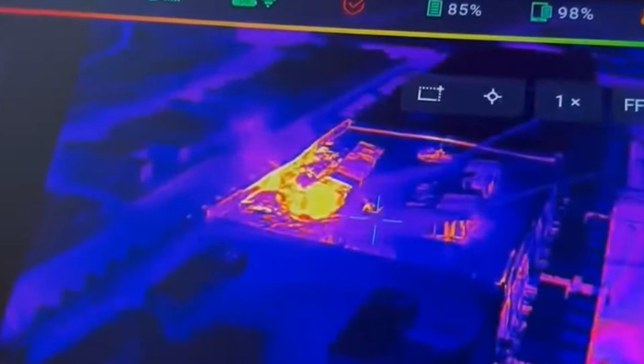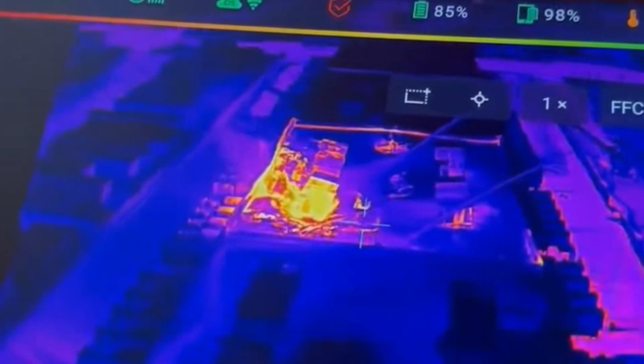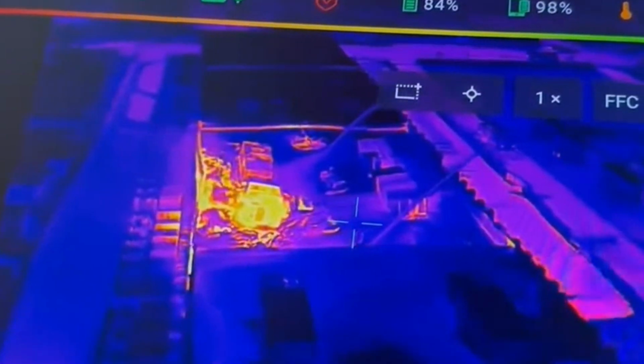On the plus side, it does appear that this is a well-designed system. It is not a walk-in style system, the style where we've seen problems in the past. It's also not a large building like Otay Mesa, so I wouldn't expect it to burn for weeks on end. This system is designed so only one of these units should burn. The heat from the fire should not be able to extend to the next unit, causing that one to go into thermal runaway. Essentially, you're writing off just one of these units instead of multiple units if there's a fire.